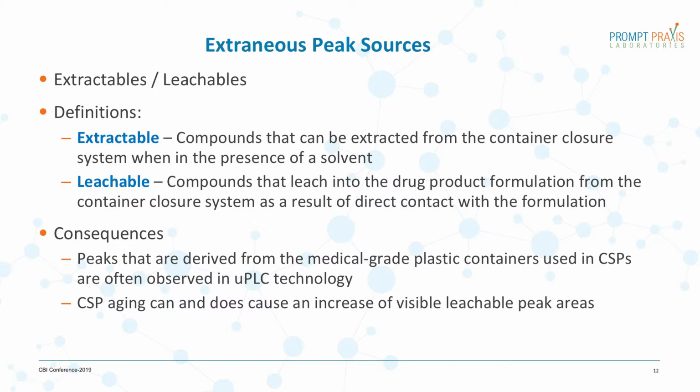And so the consequences are that there are peaks that are derived from these materials that do appear and are encountered in chromatograms. And in fact, we have seen that the longer that CSP is in contact with that surface over your 30, 60, 90, 120 days, those particular peaks may grow in peak area count.